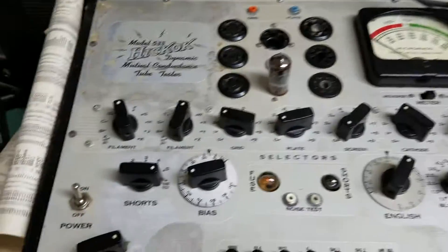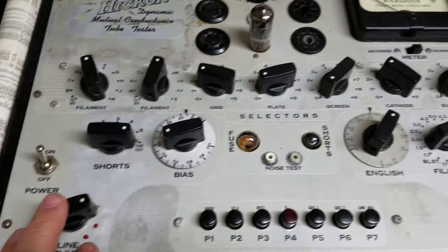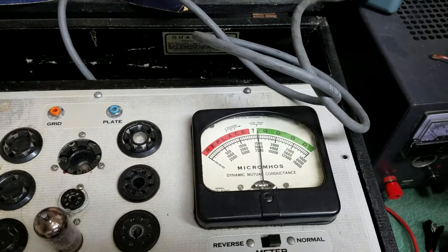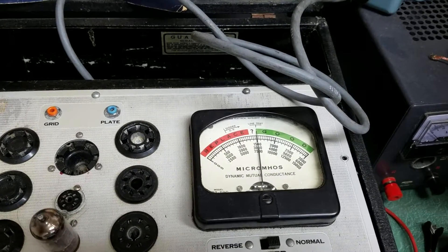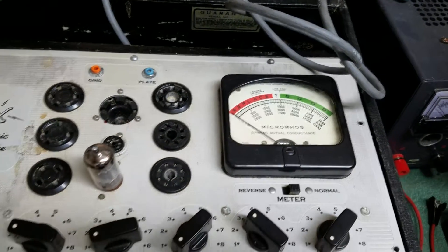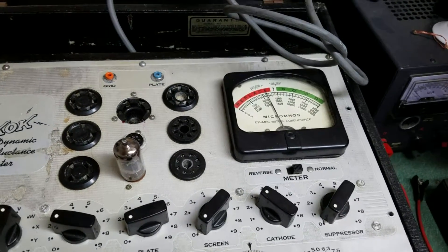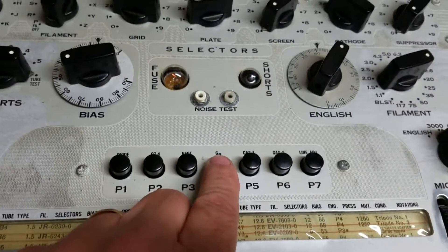I already tested one earlier. Here's the line adjust right here, and as you press P7 up here, you'll see that we got it set pretty close to the line test up there, so the meter works nicely.